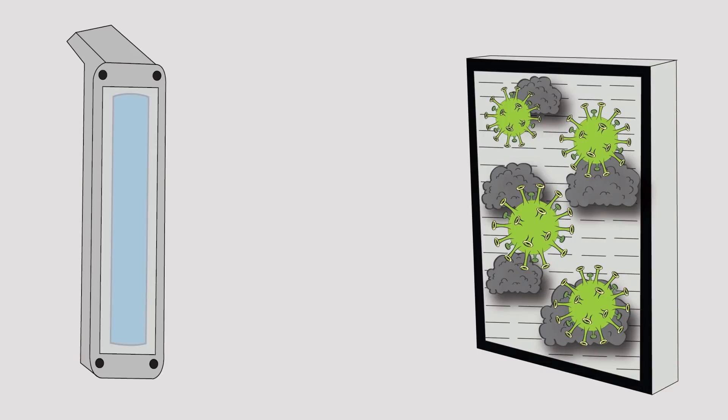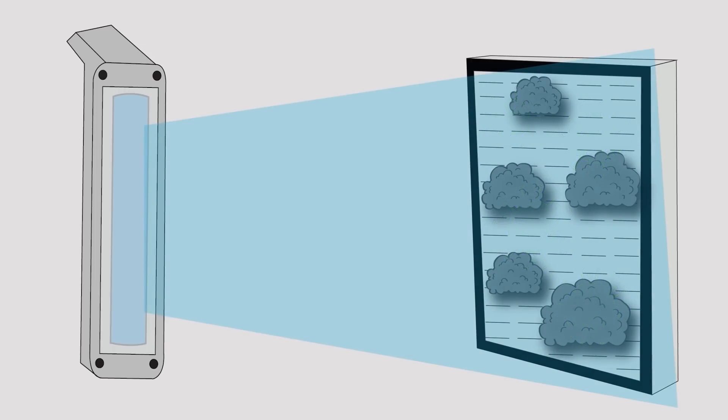We additionally back all of our filters with UV light. That's not something that comes from CDC and AIA, but it is known practice in the industry that if you catch those particles that have viable viruses on the back of the HEPA filter and you bathe that back of the HEPA filter in UV light, you will sterilize the virus. Once you sterilize the virus, it's no longer able to reproduce. Even if you were to ingest it, it can't contaminate you because it can't reproduce in your body.